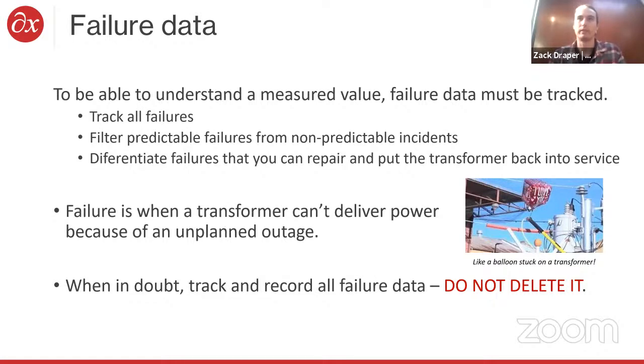And you can filter the failures that are predictable versus not predictable. For example, if a raccoon gets inside a bushing and fails a transformer, that's not something that's predictable by dissolved gas analysis, right? So in some cases, it's not useful for predicting failure. But it's important to still collect all of that information so that we understand what failure looks like, and then we can figure out how that relates to dissolved gas analysis. And for us, failure is anything where the transformer is unexpectedly taken out of service, when it can't deliver power.